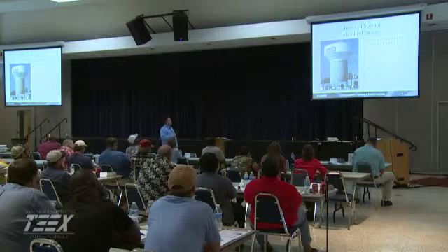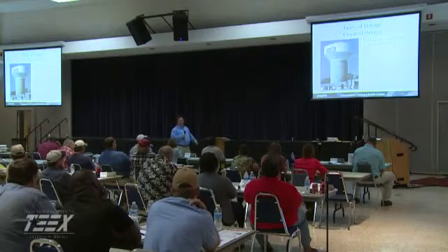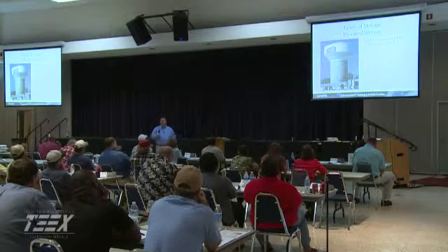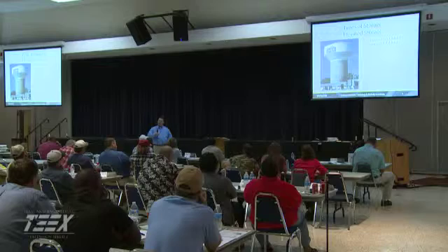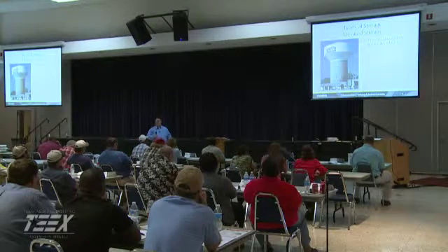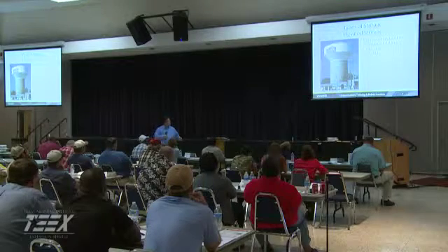Now, the purpose of them is to help maintain your water pressure in your system. They do this by simply sitting on top of your system and allowing gravity, the force of the gravity, to push down on that system and provide a consistent, even pressure. For every 1 foot of water you have in that tank, it exerts 0.433 pounds of pressure.